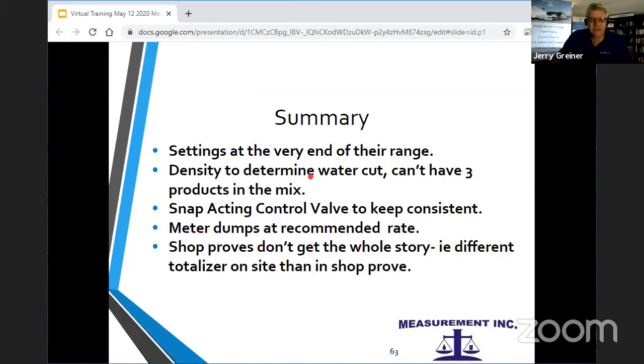Secondly, if you're using a density to determine a water cut, you can't have 3 products in the mix. You have to have 2 products in the mix. If there's a third product, using density to determine the water cut doesn't work well. It's also the same if you have different densities of oil that can vary going into it. If you don't know the density of the oil and the water, using the density to determine water cut does not work well. Use a snap acting control valve to keep things consistent.